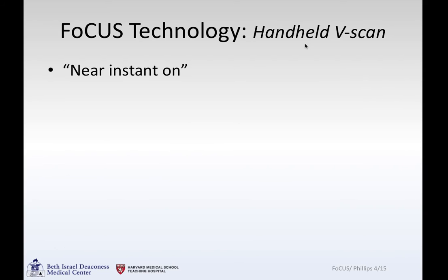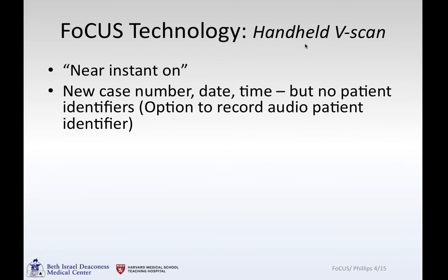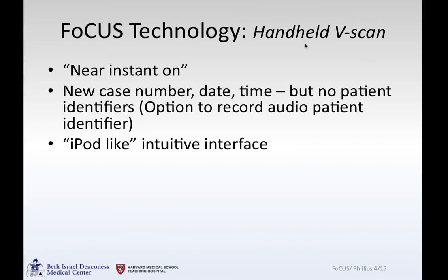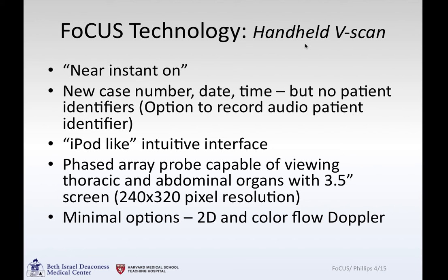A brief word about the technology. We use the V-scan: flip it open and it turns on almost instantaneously. It identifies a new case number, date, and time, but no patient identifier. You have the option of recording audio over each study to remind yourself what you're looking at. There's an iPod-like intuitive interface, a phased array probe, and a 3.5-inch screen with 240 by 320 pixel resolution. You have options of 2D and color flow Doppler, and you can make post-hoc distance measurements. Here's the unit with the heart on the screen.